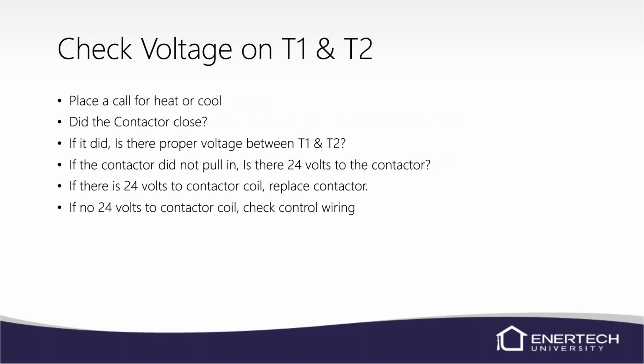Go ahead and place a call for heating or cooling. You can do that with the thermostat or the jumper wires. And again, make sure it's in test mode so we're not waiting on that 5-minute delay. And see if your contactor closed. If it did, make sure you check the T1 and T2 at the contactor to make sure you've got proper voltage, that we're not dropping a leg through the contactor, because that'll cause the compressor to overheat real quick if you give it 120 volts or 110. You're only getting one leg of power, so it won't take long for it to overheat.